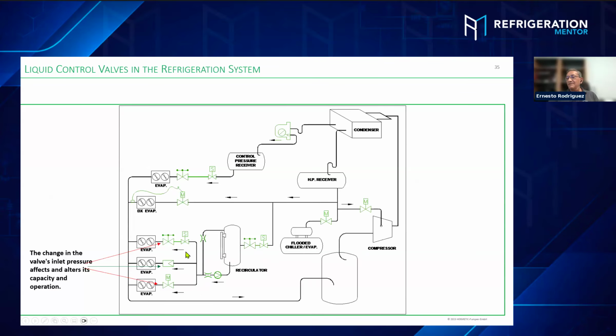Okay, for example, we have the pump. We have the hand expansion valve. You need to turn how many? Okay, 3 turns to keep the differential pressure across the valve, X differential pressure. When you reduce the pressure right here, for a bypass, for VFD, sometimes they reduce the flow on the frequency drive or use a bypass to compensate this flow instead of a differential pressure regulator.